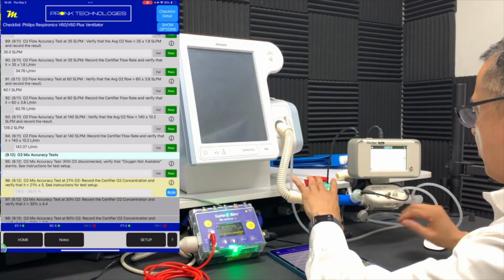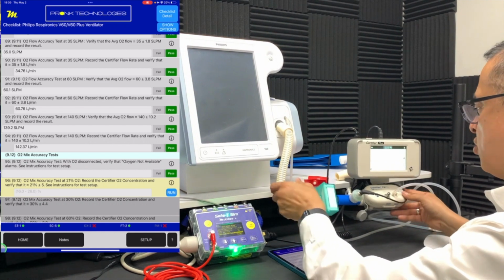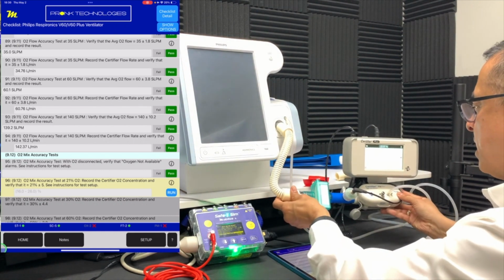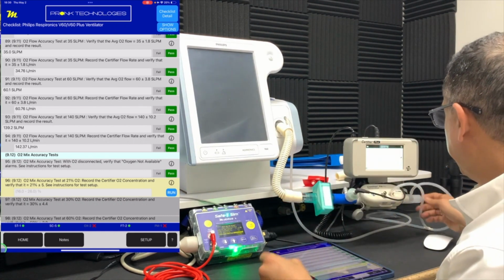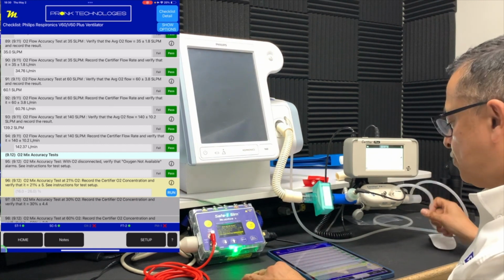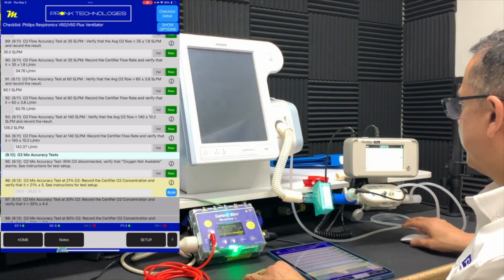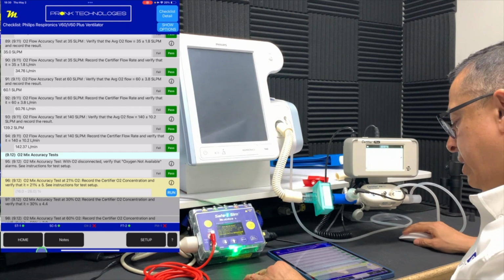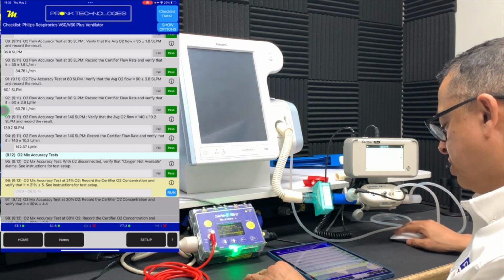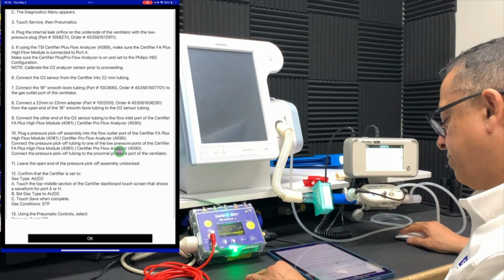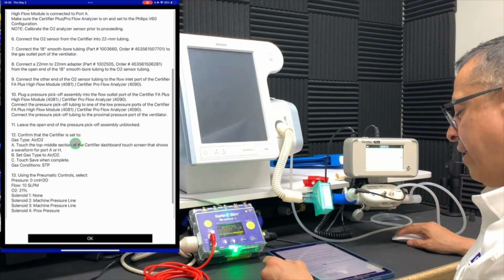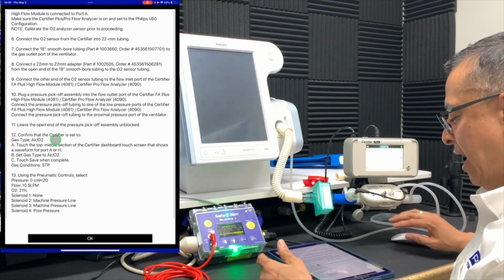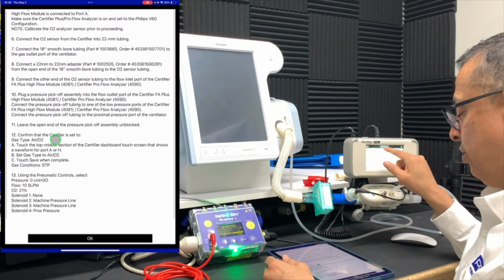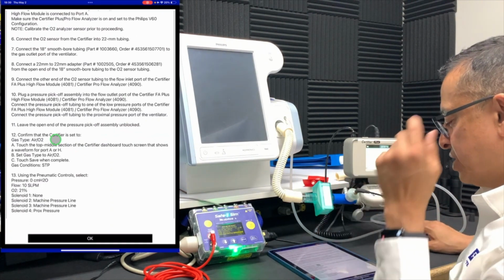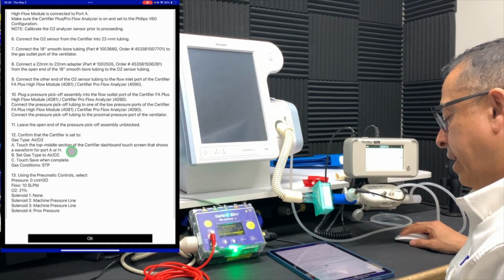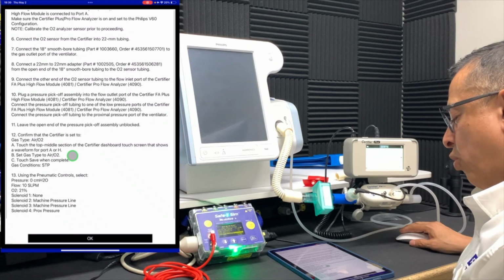And we've got it configured properly. Again, always making sure there's no leaks in the system. You've got it set up optimally so we don't have any errors in our measurement. And we also want to make sure we've configured our certifier properly. Again, if we go back to our instructions, you can see here it wants to make sure we've set up the certifier for measuring air and O2, which I've done as well. Set it up for gas conditions STP and configured my waveform ports accordingly.